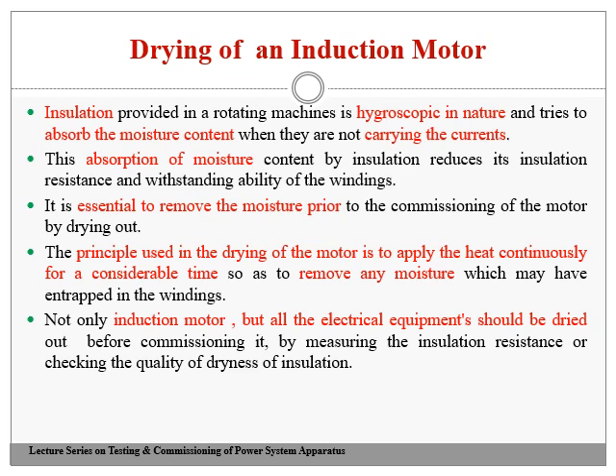The principle applied is allowing a current through the induction motor so that we can apply heat continuously for a considerable amount of time, 6 to 7 hours, even 8 hours, to remove the moisture content which may be entrapped in the induction motor's insulating medium.